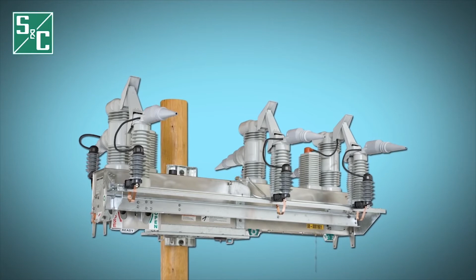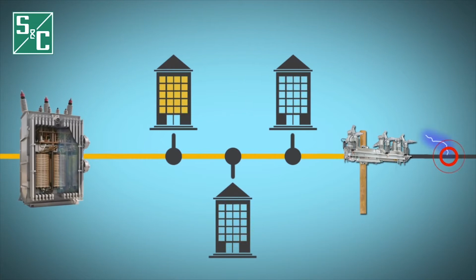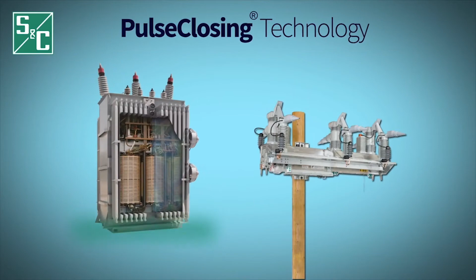S&C's IntelliRuptor Pulse Closer Fault Interrupter uses a unique innovation called pulse closing technology. Pulse closing technology uses a small pulse of current to detect the presence of a fault. This results in less than 5% of the energy to test for the presence of a fault compared to reclosing. Pulse closing technology detects the presence of a fault, but without the harmful fault multiplier effect, resulting in better reliability.